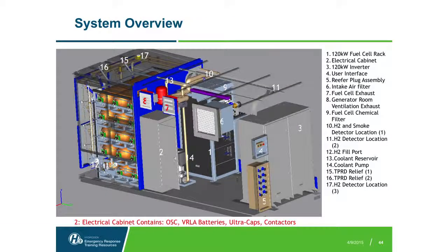So here's an overall layout, obviously without the walls and ceiling. You'll see that in a moment, where the unit will be fueled. Here's the PRD or vent releases on this end. This is the inverter. This electrical cabinet includes the system controller, batteries, ultracapacitors, and contactors. Here's the user interface with the reefer plugs on the opposite end. This is really the only place that the users will be interfacing with the unit. Since it'll be fueled by other personnel, that'll happen at this end. And you'll see a man door, so someone can enter this room, but there's really no reason for any of the operators to be entering that space.